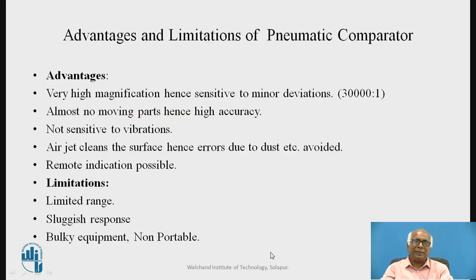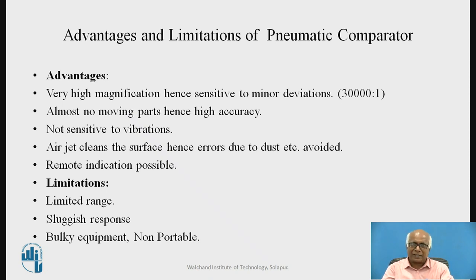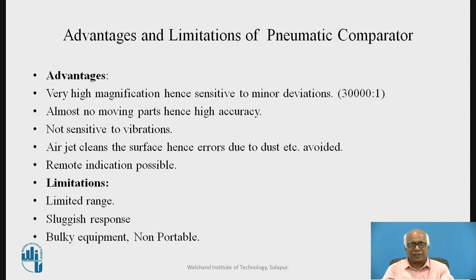Advantages of pneumatic comparators: very high magnification, making the comparator very sensitive to even minor deviations — the magnification range is 30,000 to 1. There are almost no moving parts in the comparator, hence very high accuracy, because there is no friction and no wear and tear. So over time, there will not be any loss of accuracy.